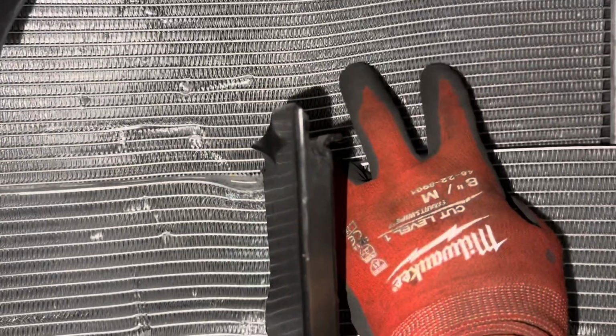And behind it is glycol. So the second one behind it, up here where my finger is, that's not a condenser, that's a glycol heat exchanger. This one is refrigerant, but that can't be the only one. There's got to be one behind it, so we have a third one to look for.